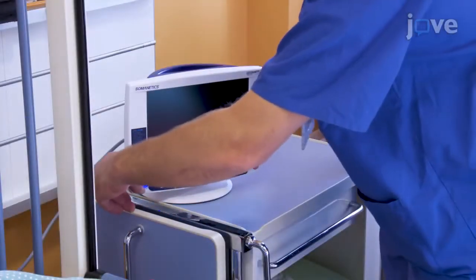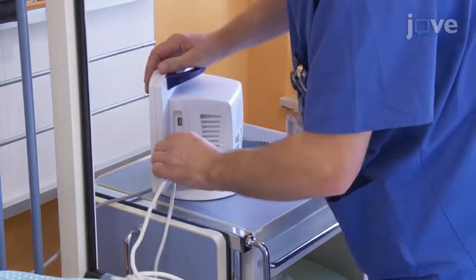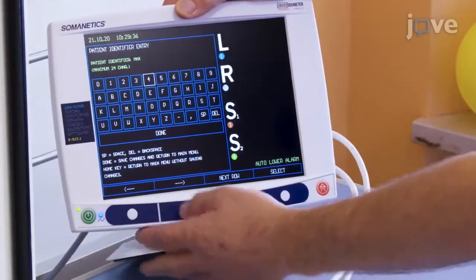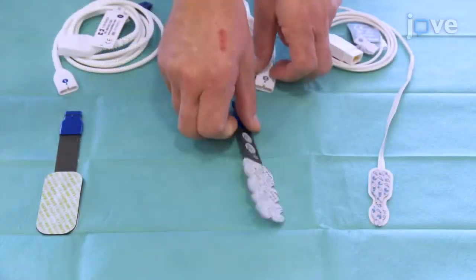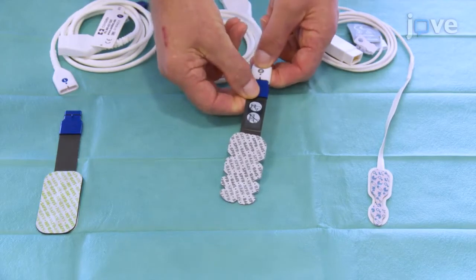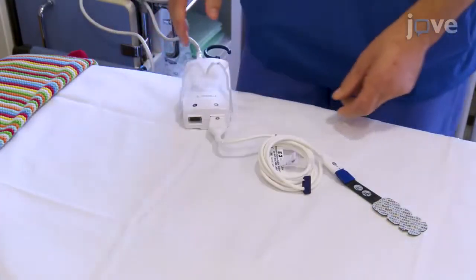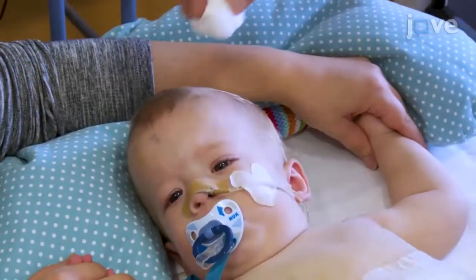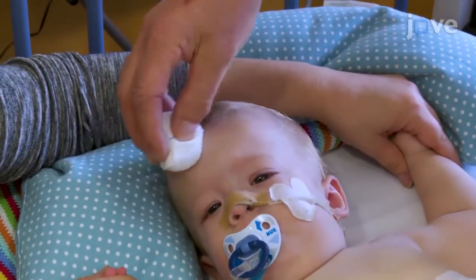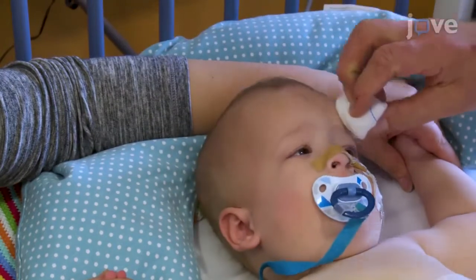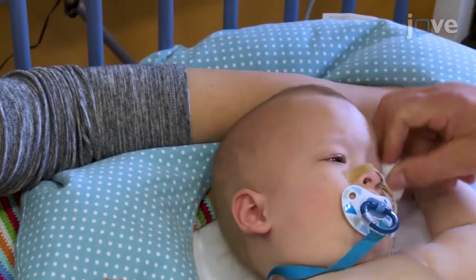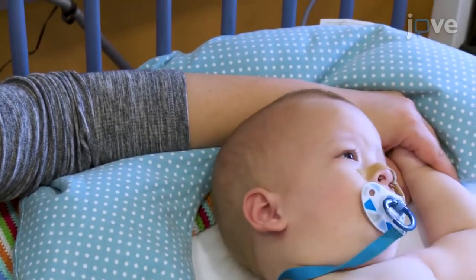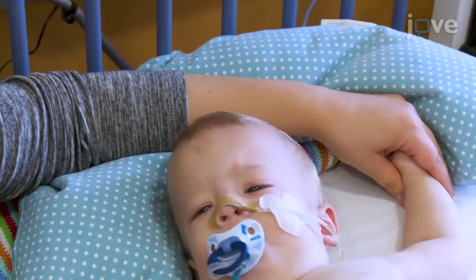Begin by turning on the NIRS device and connecting the preamplifiers. Enter the patient's data and select the proper probe according to the patient's weight and intended site of use. Connect the probe to the preamplifier. Make sure that the patient's skin is clean and dry for optimum adhesion. Dry the skin with a swab if necessary, being very careful, or omitting cleaning if the skin is vulnerable.